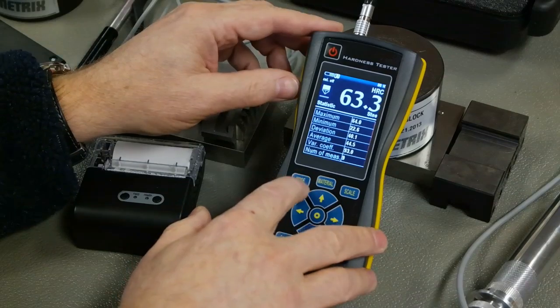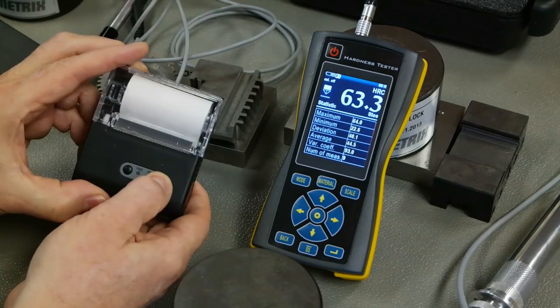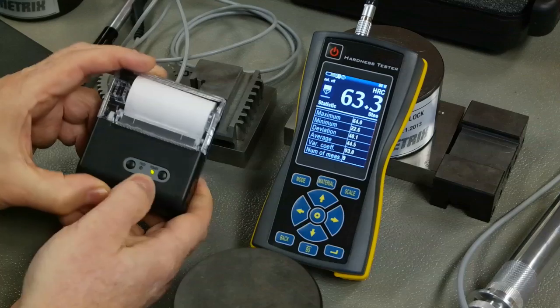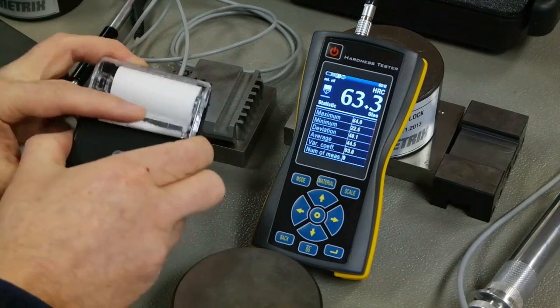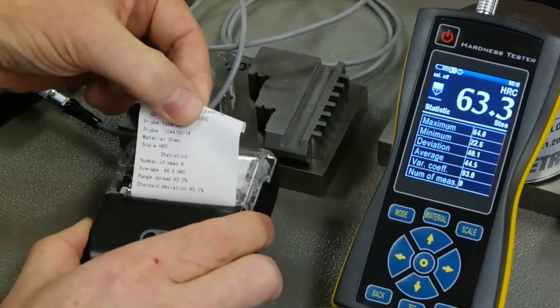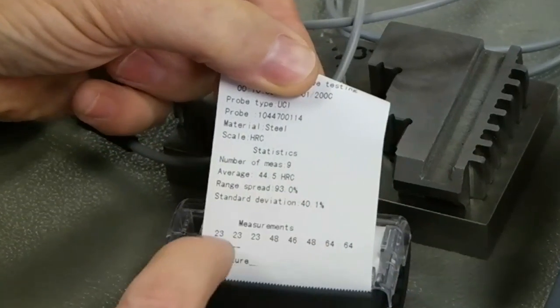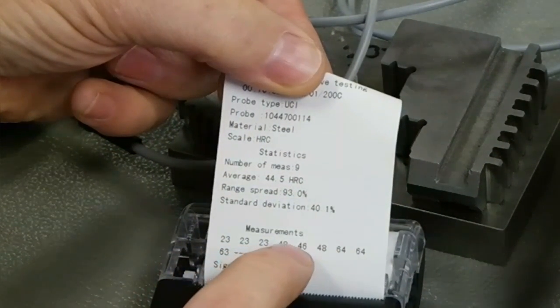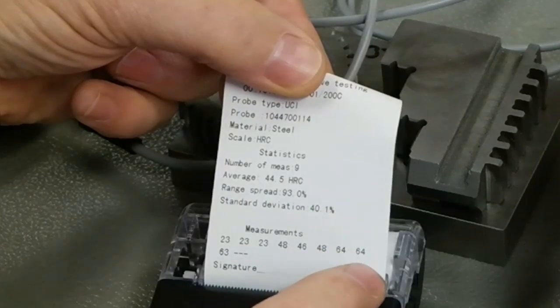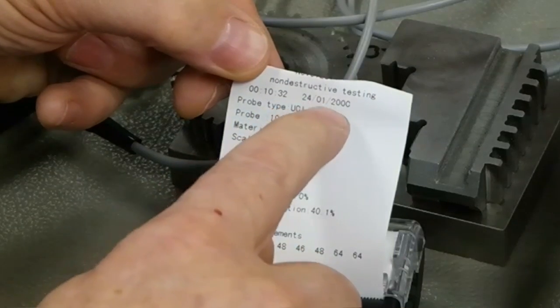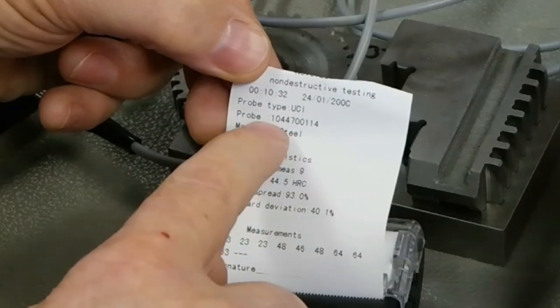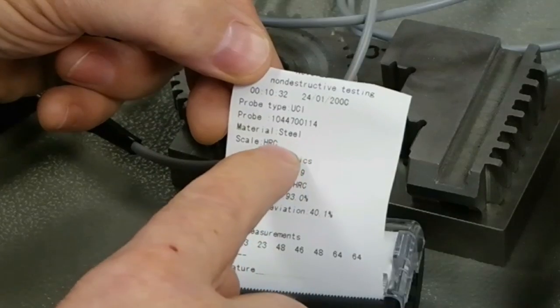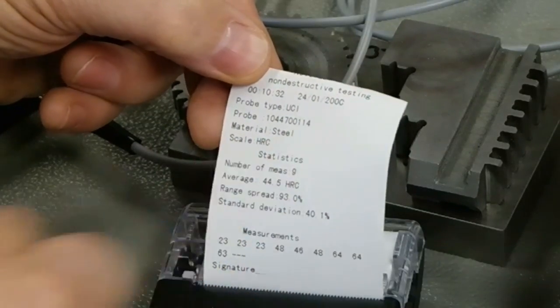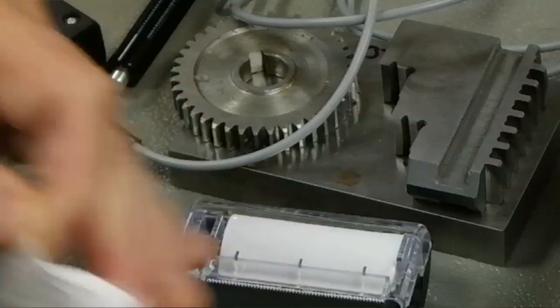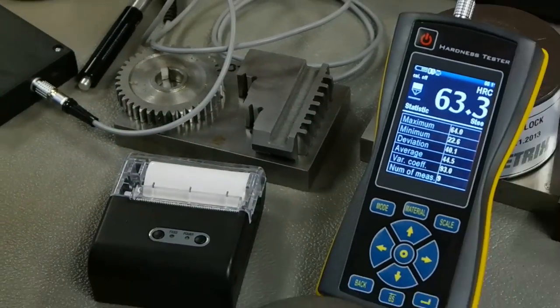If I want to, at any point, I can then print to my wireless printer. I'll just power it on. Button's on, I just hit the middle mouse button, and immediately it does a printout. So I can see I have 23, 23, 23, 48, 46, 48, and 64 and 64. I can sign this. The date is shown when the test was done. That's a UCI probe, the serial number of the probe, the fact that I'm testing steel, and it's HRC, and there's all the stats. And of course this can be taken off and included with your test part.